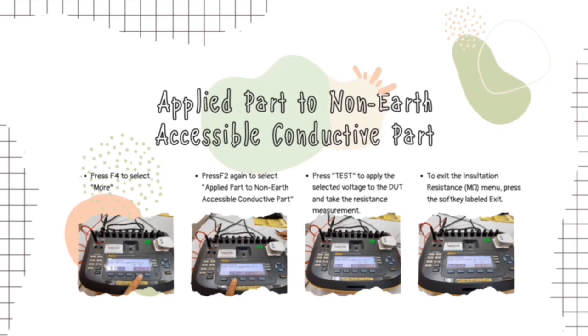Next is applied part to non-earth accessible conductive part. At this part, we must select F4 for more. Then press F2 again to select applied part to non-earth accessible conductive part. Then press test to apply the selected voltage to the DUT and take the resistance measurement. To exit the insulation resistance, press the soft key label exit.